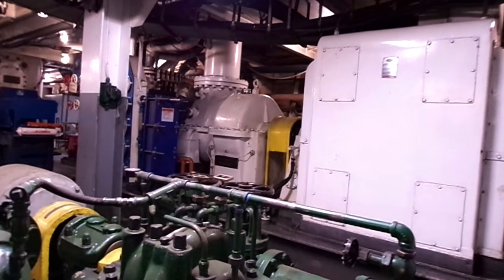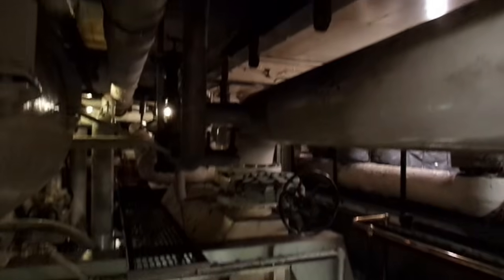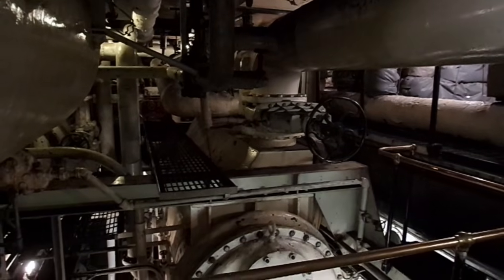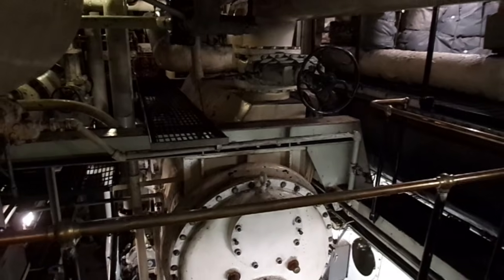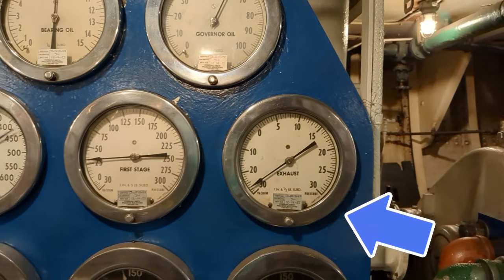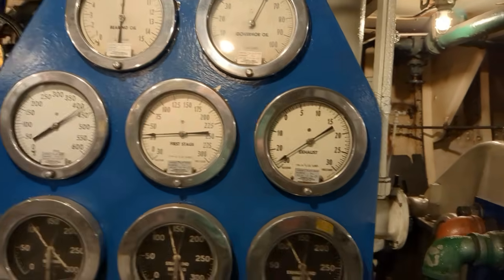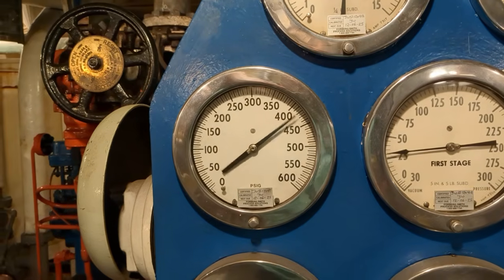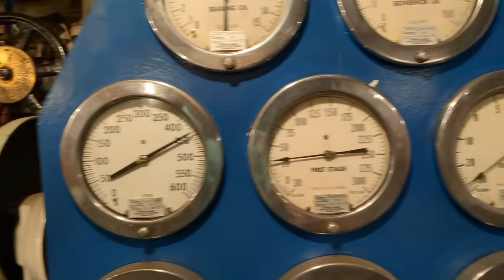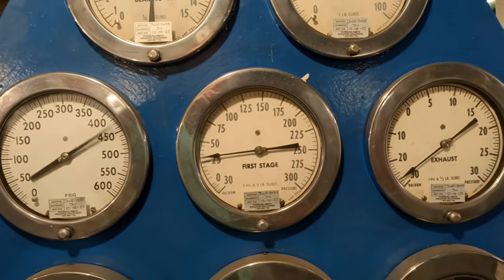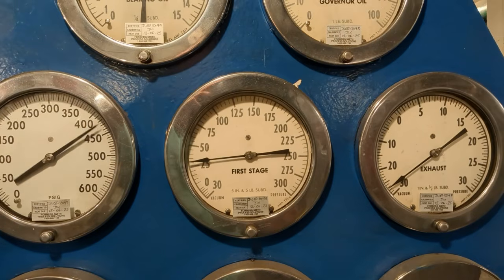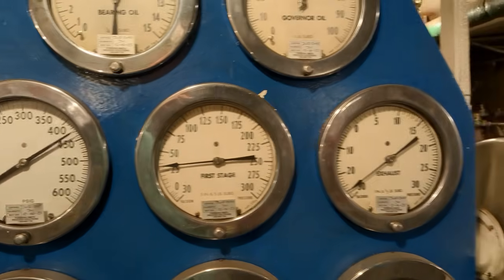The turbine itself consists of a Curtis impulse stage followed by a multi-stage low-pressure turbine. After passing through the turbine, the steam exhausts into the condenser where a vacuum of about 28 inches of mercury is maintained. These gauges show the operating conditions, with more than 400 psi ahead of the nozzles and about 30 psi after the first stage impulse wheel.